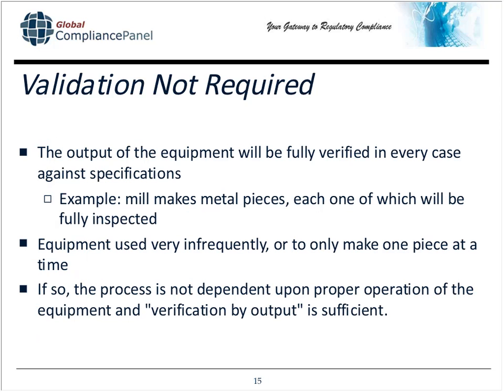Having said a moment ago that there is equipment that does not require validation, here's what you have to do. You have to make sure that the output of this equipment is fully verified in every case against specifications. That's an example of situations where validation is not required.